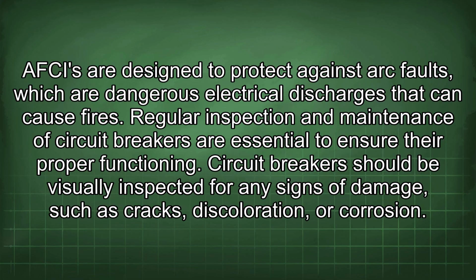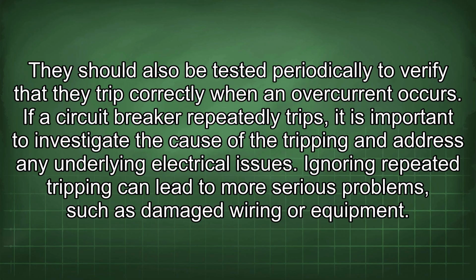Regular inspection and maintenance of circuit breakers are essential to ensure their proper functioning. Circuit breakers should be visually inspected for any signs of damage such as cracks, discoloration, or corrosion. They should also be tested periodically to verify that they trip correctly when an overcurrent occurs. If a circuit breaker repeatedly trips, it is important to investigate the cause of the tripping and address any underlying electrical issues. Ignoring repeated tripping can lead to more serious problems, such as damaged wiring or equipment.